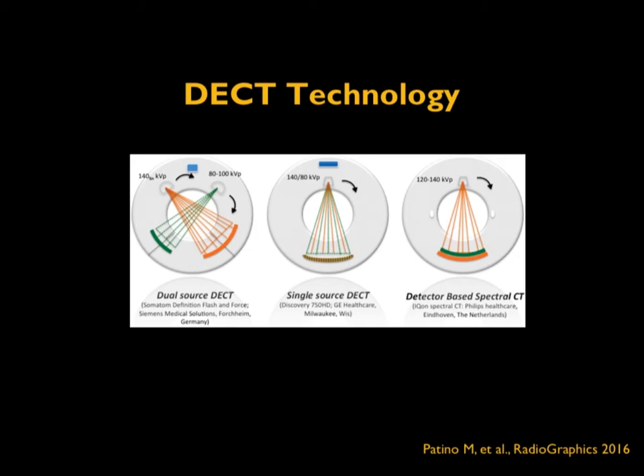The three main distinct methods are: first, dual source CT with two x-ray tubes set at two different tube voltages, automatically producing two different energy beam spectra; second, a single source where the x-ray tube switches between two different kV at every instance; and third, a single source with a dual-layer detector — the front layer absorbs the majority of low energy photons and the back layer absorbs the high energy spectrum. The fourth method is simply scanning the same area twice at two different tube voltages.